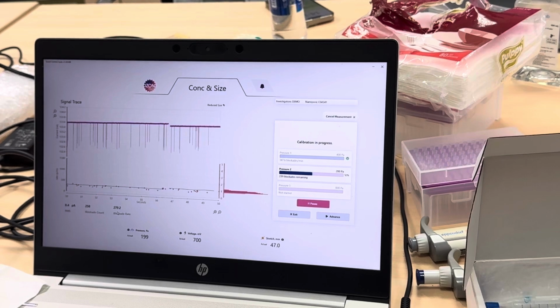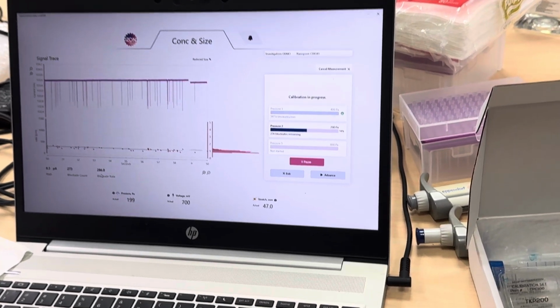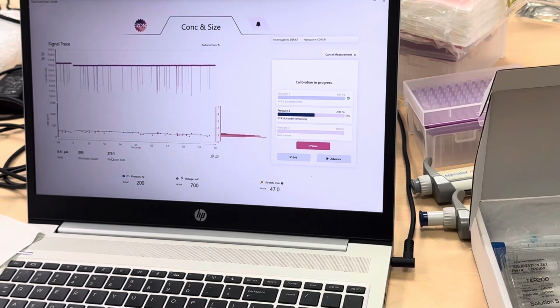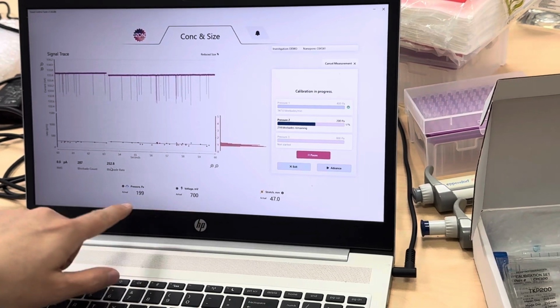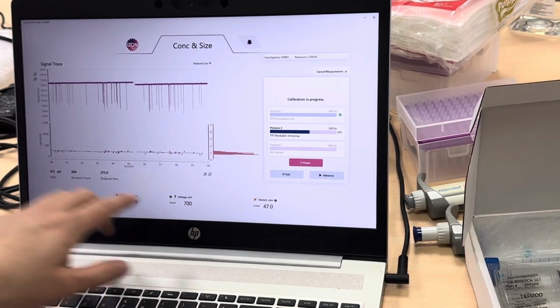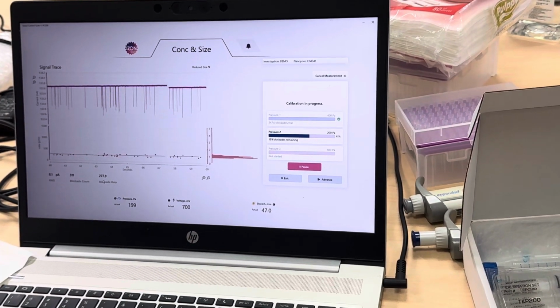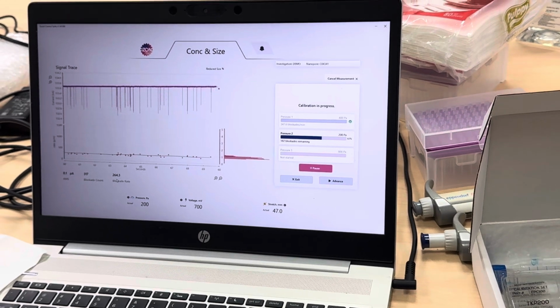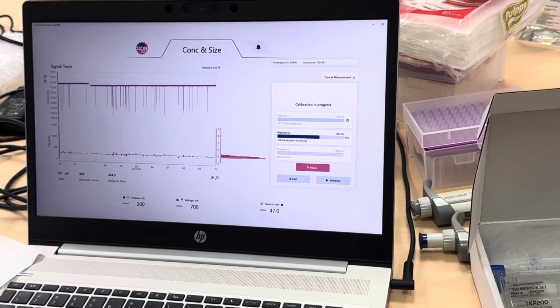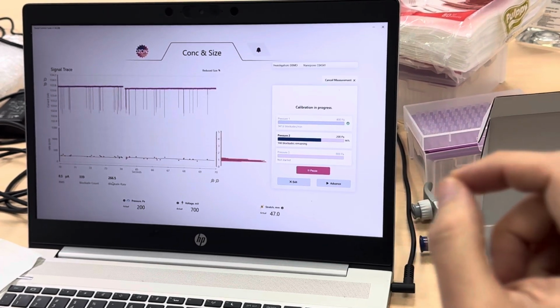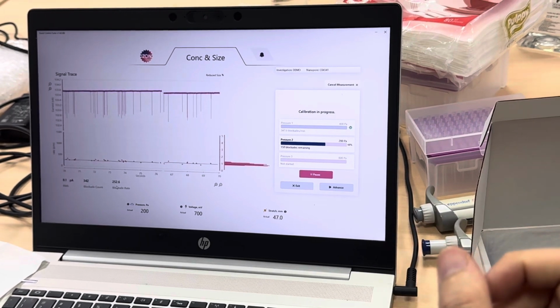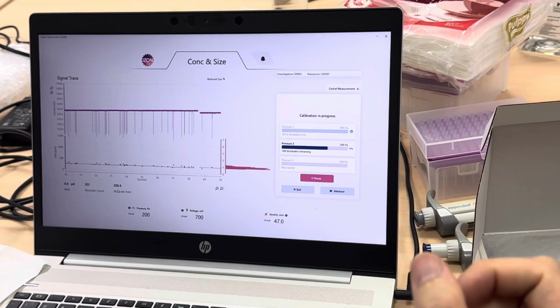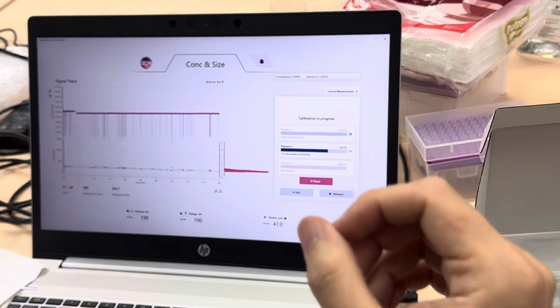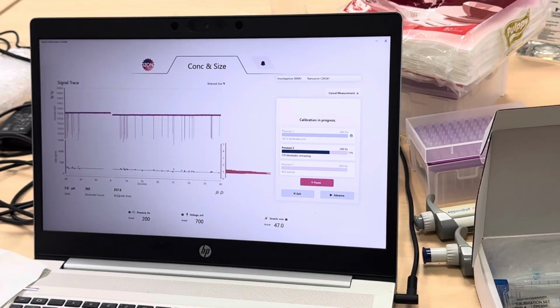will automatically calibrate. Yeah, because the system is running the calibration and the sample at the same parameters, like the voltage, the stretch, the pressure. So the system will use the calibration data to form a linear strip because it's linear. And then when you do your samples, later we do the analysis, so use the calibration linear strip to find the correct value for your samples.